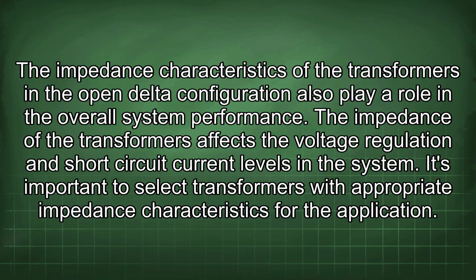The impedance characteristics of the transformers in the open delta configuration also play a role in the overall system performance. The impedance of the transformers affects the voltage regulation and short-circuit current levels in the system. It's important to select transformers with appropriate impedance characteristics for the application.